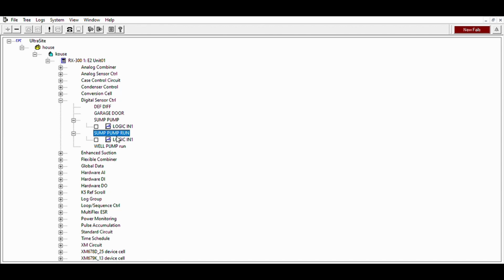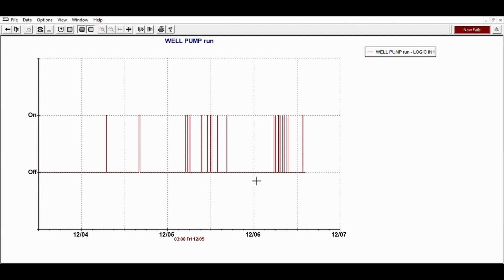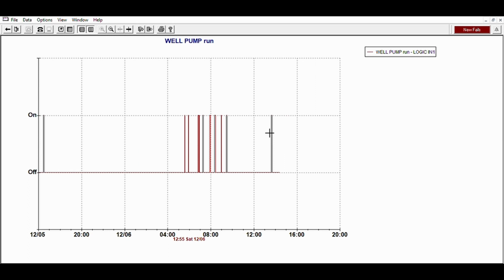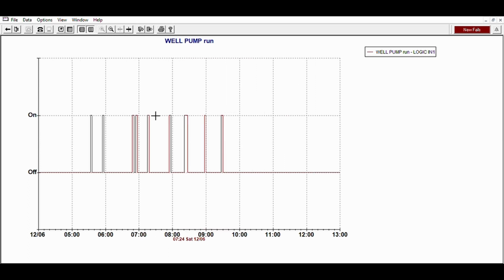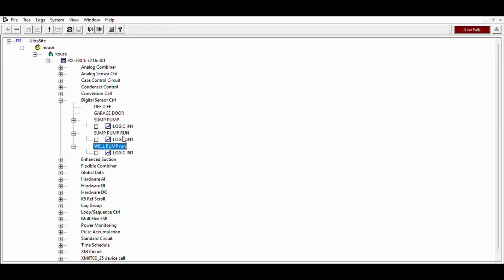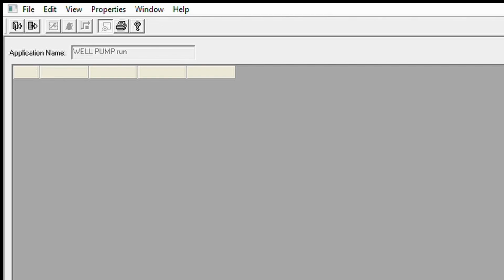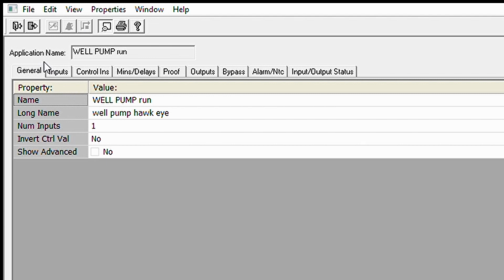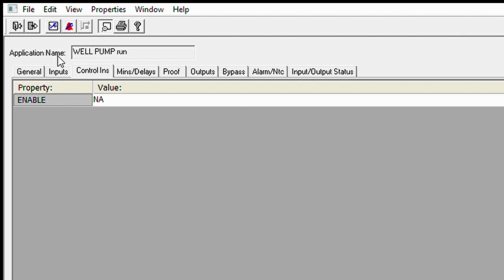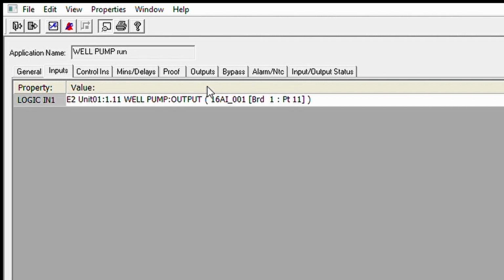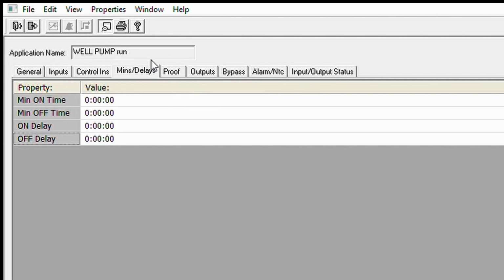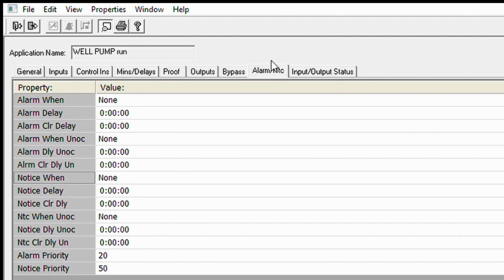And then well pump run. So another one. You look at this one, get logs. This one may not even be set up. So this is my well pump cycling. Every time it comes on, it's going to proof it. You can see between 8 and 9, it's coming on, coming off, coming on, coming off. I'm using a CT or current transducer for that. If we look at this one, edit application, this actually comes from a Hawkeye, which is a current transducer. Every time it does it, it's proofing it on and off, and it's one way you could tell how many times things are cycling on and off.